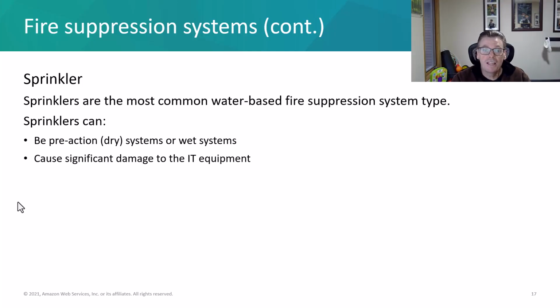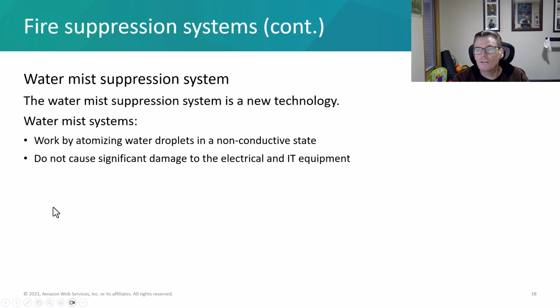Sprinklers, on the other hand, are the most commonly used water-based fire suppression type. These can cause significant damage to IT equipment. But we should know the difference between the pre-action and the wet systems. The pre-action systems have valves that open and then flood the sprinkler piping, so the piping is dry. There's no water in the piping unless the suppression system is activated, versus a wet system, which contains water in the sprinkler piping at all times. If you think about it, that wet system can be a larger risk to the IT equipment in the event that the lines corrode and start to leak, or we get some water leakage at a joint or something along those lines. So the dry systems are a little bit better.